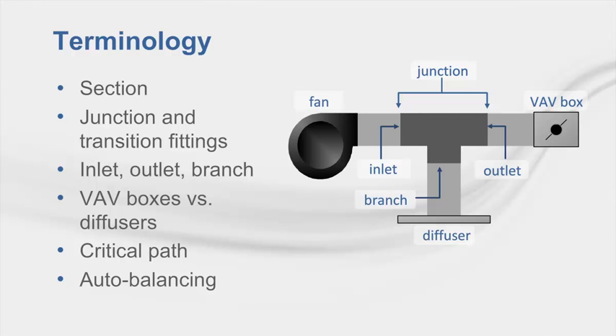The critical path has the largest pressure drop of all paths associated with the fan. Therefore all non-critical paths are over-pressurized and require resizing or the addition of dampers and orifices to balance the system. Auto balancing is a feature available within the duct configurator that allows designers to downsize non-critical paths and add dampers or orifices to use up excess pressure in the system without affecting the critical path.